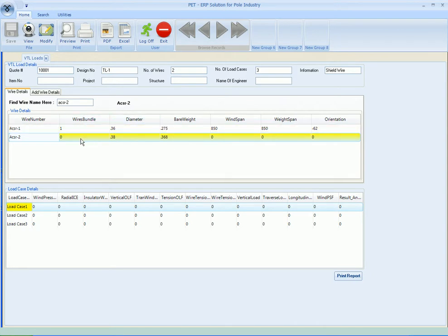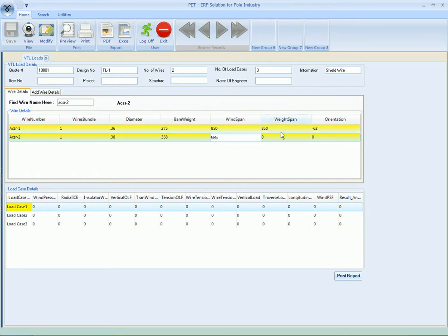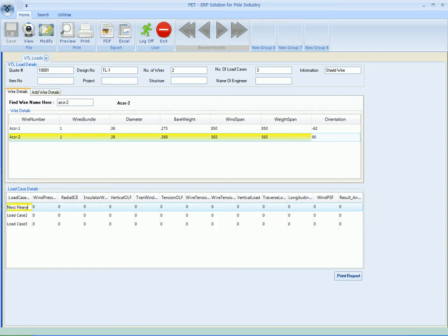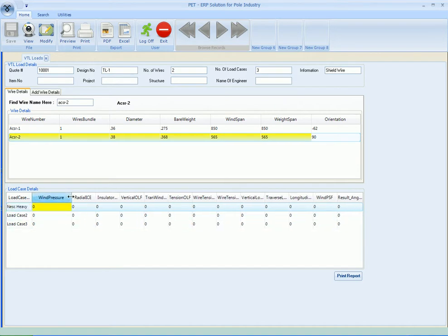Again enter the wire bundle 1. The wind span for the second wire let's say 565, the weight span is again 565, the orientation is let's say 90. Now here is the load case detail. So load case name, let's say it's first wire - first load case name is NESC heavy.